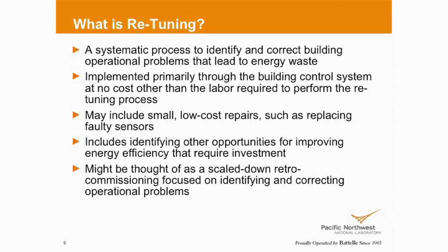There may be some repairs required, low-cost repairs, faulty sensors, perhaps an actuator - it might be a damper or a valve. But what we've seen, and we'll show this in our slides, is if we let those failures persist, it might be a $100 or $200 failure, but it can end up being 10 to 20 times that in energy.